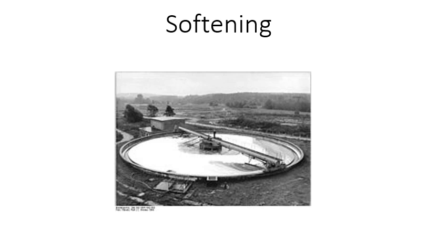Common hardness ranges: I get a lot of different ones in different places I look. We're going off Sacramento State. 0 to 60 milligrams per liter is soft water. 60 to 120 milligrams per liter is moderate or normal. 120 to 180 milligrams per liter is hard. 180 milligrams per liter or greater is very hard.